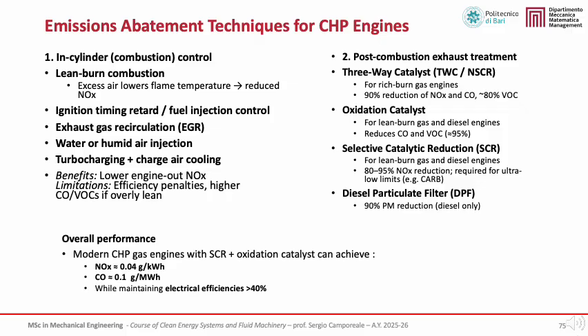In-cylinder control strategies include lean burn combustion, where excess air lowers the flame temperature and therefore reduces NOx formation, as well as ignition timing retard, fuel injection control, exhaust gas recirculation, or EGR, and water or humid air injection. Turbocharging combined with charge air cooling is also used to maintain efficiency while limiting emissions. The main benefit of these techniques is lower engine-out NOx, but they may introduce efficiency penalties or increased CO and VOC emissions if combustion becomes excessively lean.